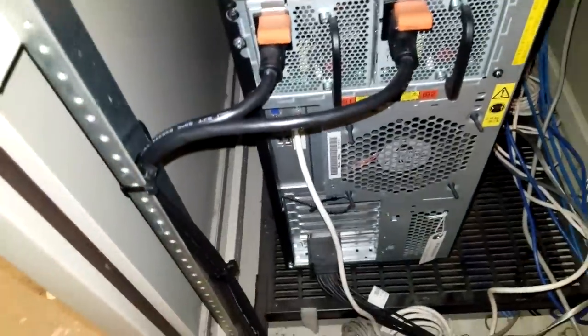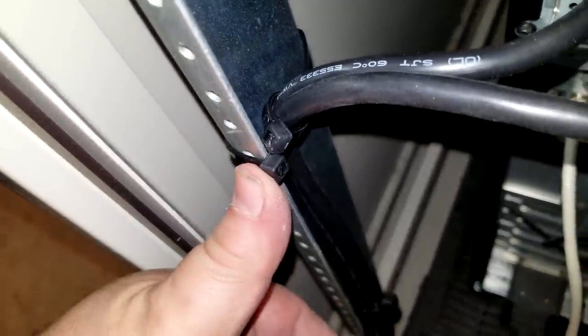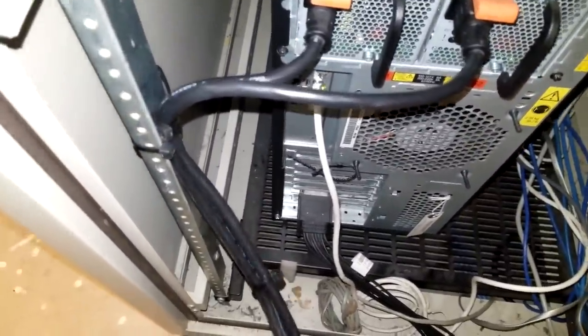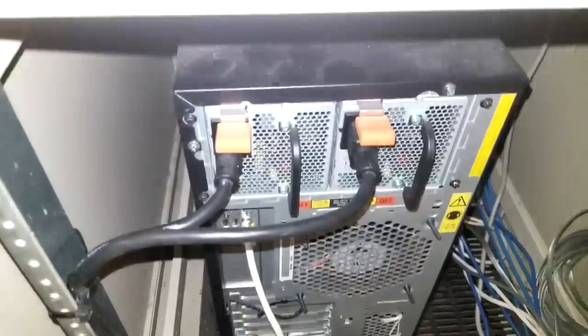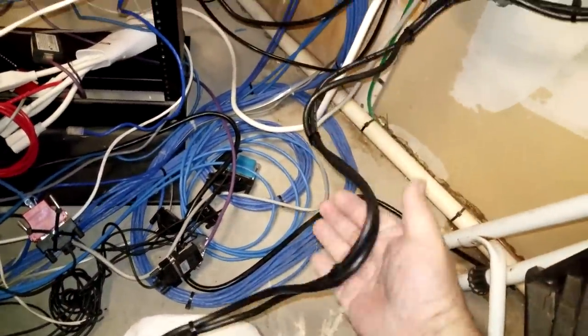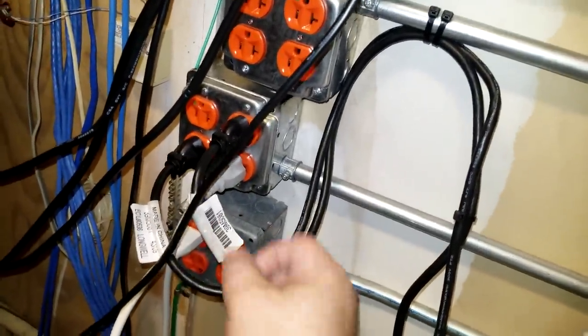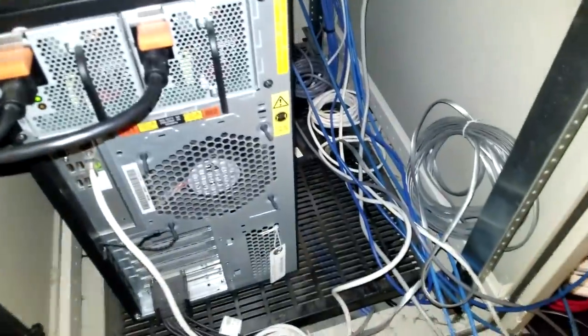Here's the solution: I run one zip tie completely around the rail but that alone won't provide enough pressure. I put another tie wrap around that one to give plenty of friction to prevent it from being pulled out. I'll probably put a second one all the way around — belt and suspenders. Then I put tie wraps throughout the cable to keep it from binding up, secure it to conduit, and leave plenty of slack so it can be relocated. This is a much safer condition where no one is going to accidentally unplug a server.